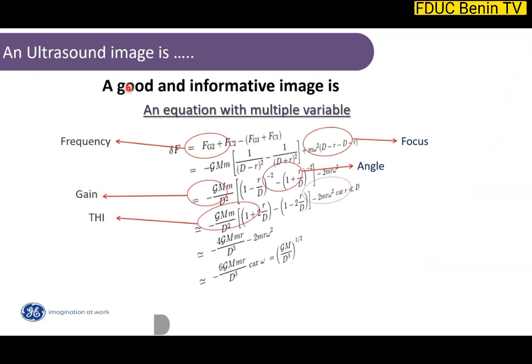So at the end, what is a good image? It's like an equation with multiple variables. You see in an image, we have the frequency that will play a big and important role in delivering a good image, the gain of the image, the focus, but also the angle, the depth, the zoom. But also what is important is that the operator and the patient are two elements that are key in the image resolution. And we're going to see now how all these elements, all these features can impact, and how we can use them in order to improve our image resolution.